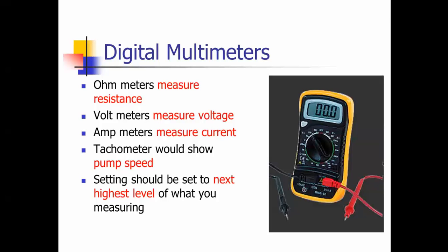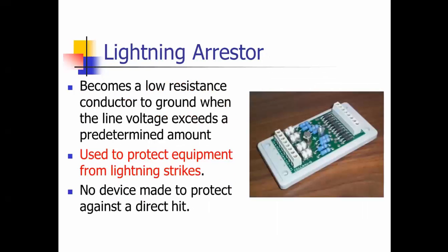A tachometer would show the pump speed, and the setting should be set to the next highest level. So if you're testing, for example, 110, you want to move it up to around 200, the next highest level, so you don't knock out the fuses in your meter. A lightning arrestor becomes a low resistance conductor to the ground. Generally, they're used to protect equipment from lightning strikes. If you get a direct hit, you're going to fry it anyway. So they're made to protect against surges and things like that. But if lightning hits near the vault where your equipment is, it'll probably burn it up.